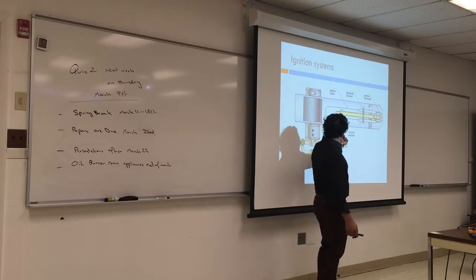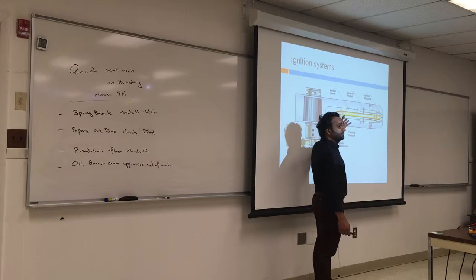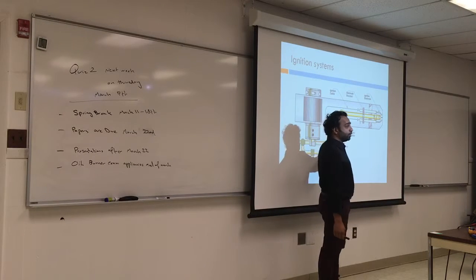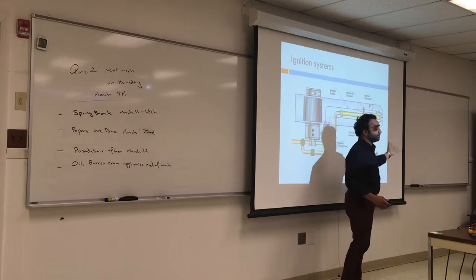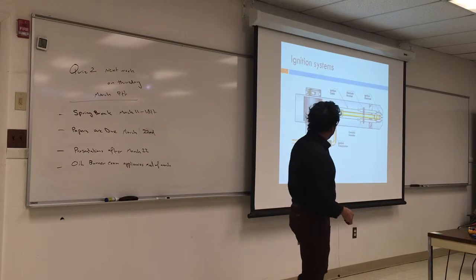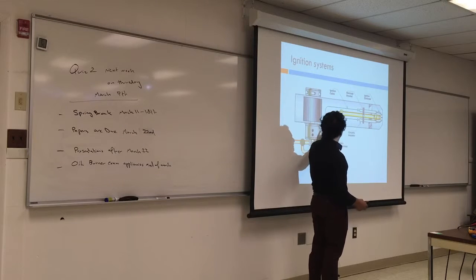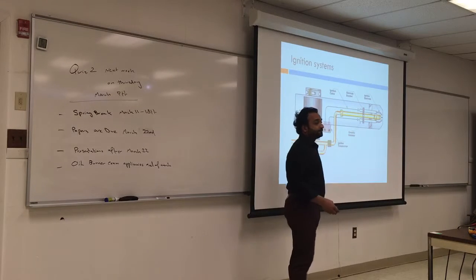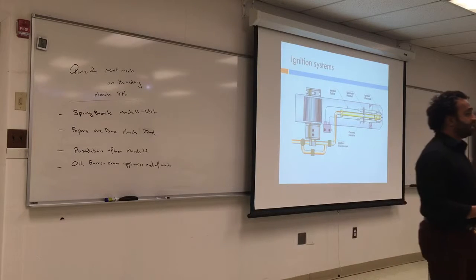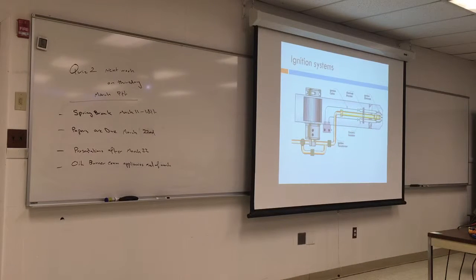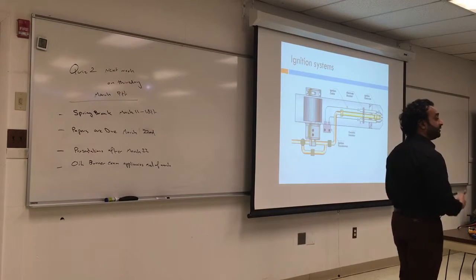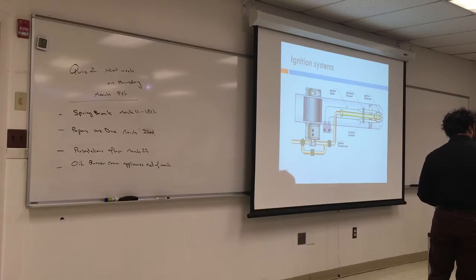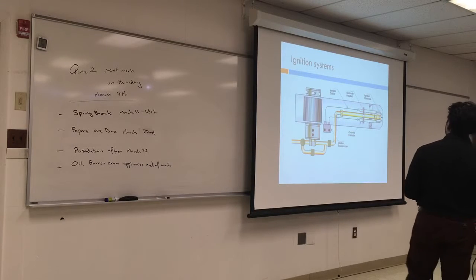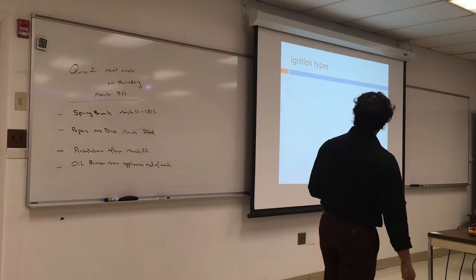You loosen your igniter from the side, and sometimes if they're short enough, you can pull them to the top. If it's too long, you have to take out the burner and pull them out. The transformer is usually supposed to be at the top, and in some models like Riello or Beckett, they have a different kind of control. They're very small and they're included with the primary. So you see the primary and the control all together in one component. It will look something like this, and the small control will have its own transformer. So make sure you identify where the components are.